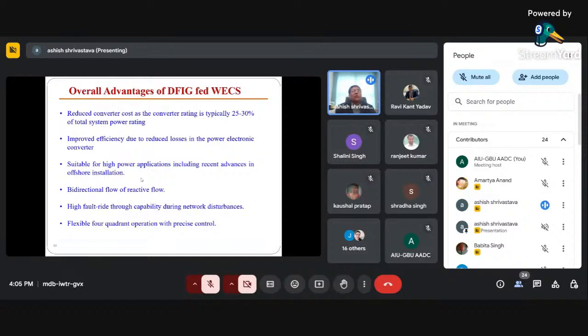So reduced converter cost, as the converter rating is typically only 25 to 30% of the total system power rating. That is the major advantage. It can improve efficiency due to reduced losses in the power electronic converter. So efficiency can improve to a large extent because the power electronic converter being used has a much lesser rating, since your voltage is only slip times the frequency. Suitable for high power application, including recent advances in offshore installation. So mostly for offshore installation and for high power rating, this is preferred.